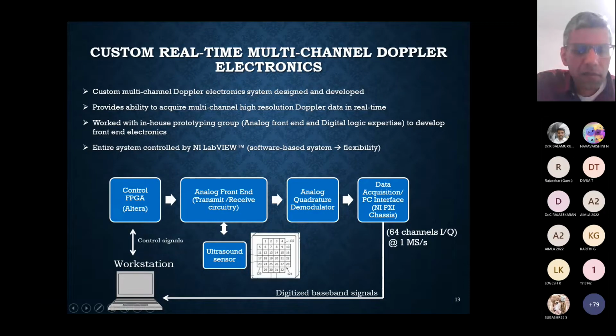So this is an example of how we developed the data acquisition system. It was completely developed in-house. We have a control software which is done using an FPGA. There's an analog front end. This is where all the transmit receive circuitry happens. We want to acquire data and convert it to baseband. So we have a quadrature demodulator. And we relied on National Instruments LabVIEW and National Instruments data acquisition systems to be able to acquire data from all 64 channels. So we have 32 transducers. Each transducer is giving you in-phase and quadrature data. So that's why we have 64 channels.